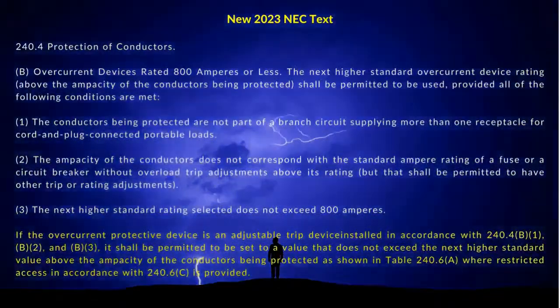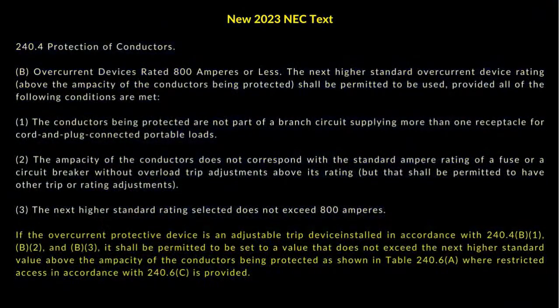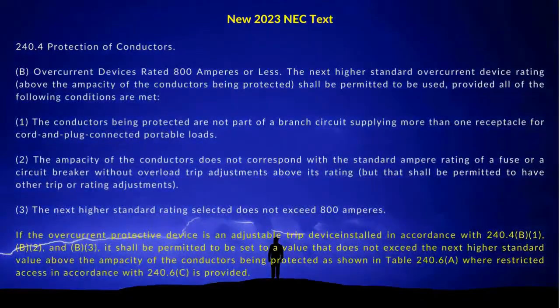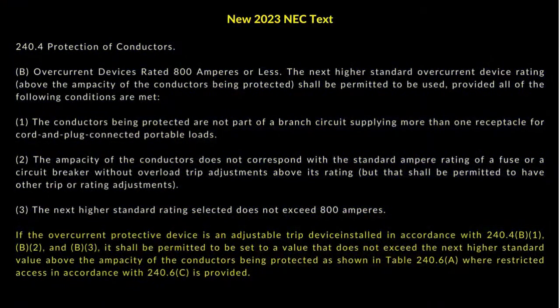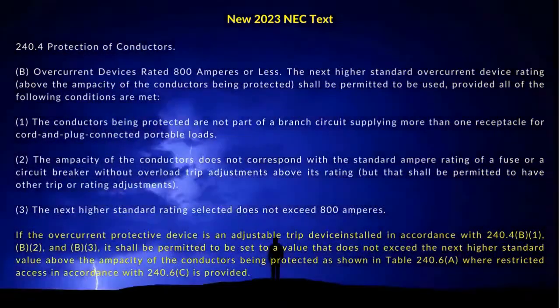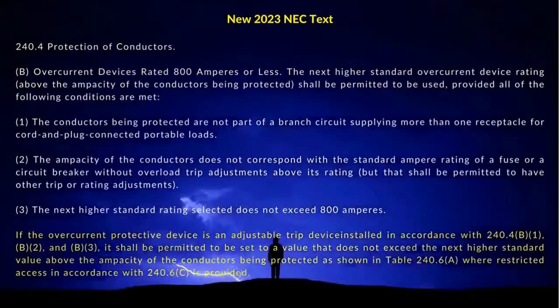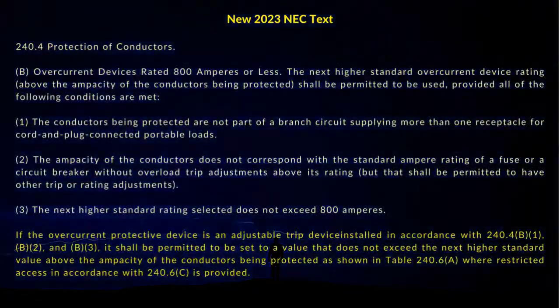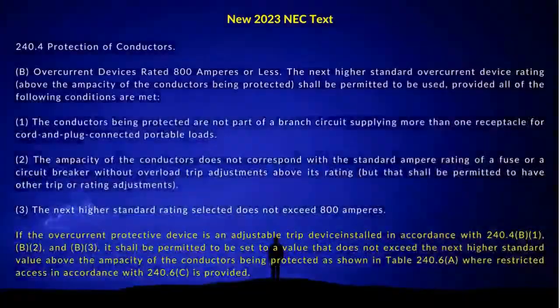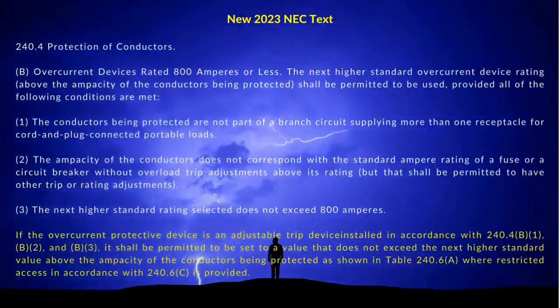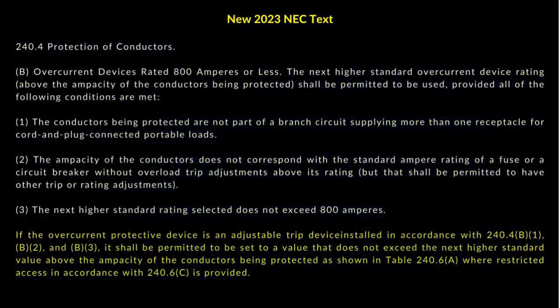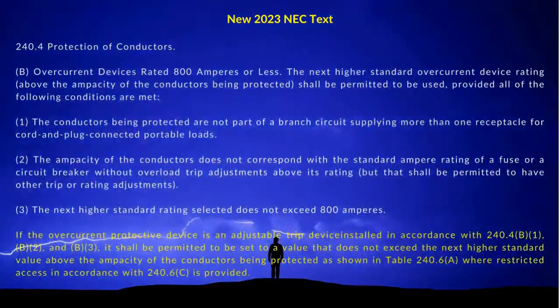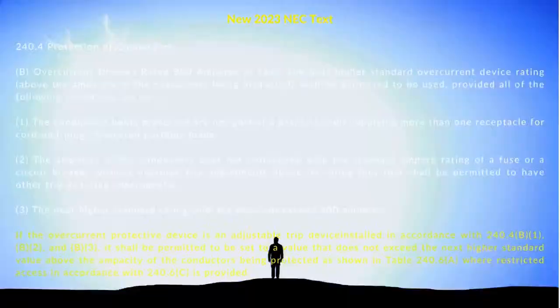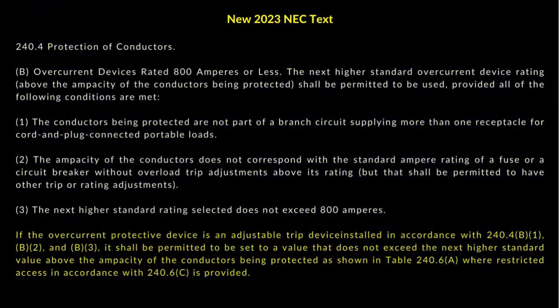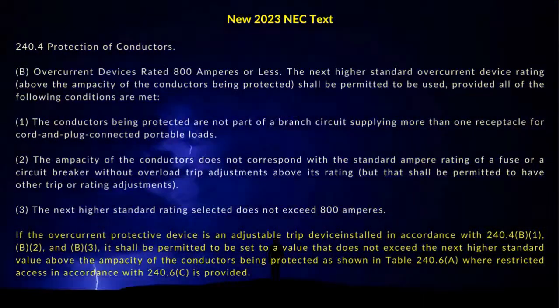A new paragraph has been added to 240.4(B) that states the next higher standard overcurrent device rating, above the ampacity of the conductors being protected, shall be permitted to be used, provided all of the following conditions are met. Subdivision B1 states that the conductors being protected are not part of a branch circuit supplying more than one receptacle for cord-and-plug-connected portable loads. Subdivision B2 states that the ampacity of the conductors does not correspond with the standard ampere rating of a fuse or a circuit breaker without overload trip adjustments above its rating, but shall be permitted to have other trip or rating adjustments. Subdivision B3, the next higher standard rating selected does not exceed 800 amperes.